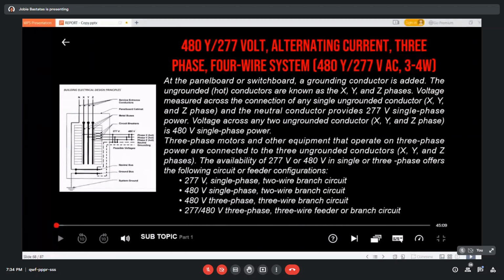Next is the 480/277 volt alternating current three-phase four-wire system. This is the common electrical service in most modern commercial buildings. The Y in the system relates to a wye winding configuration of the secondary windings of the transformer, producing a three-phase current. Large retail shopping malls, schools, grocery stores, supermarkets, and office buildings use this system for its 277 volt fluorescent lighting capabilities.